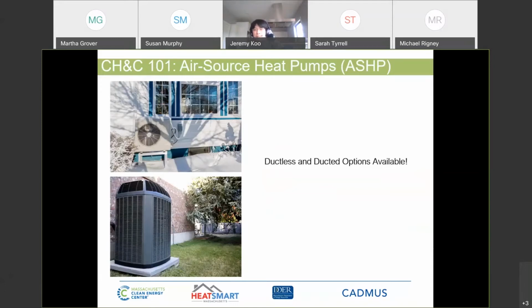Fortunately, in the last decade, there have been a lot of technology advances, including cold climate air source heat pumps, which provide high efficiency at temperatures of 5 degrees and lower, and can keep providing heat as low as anywhere from -13 to -22. That's just air temperature, not including wind chill. So these systems are certified and tested by one of the national regional energy efficiency organizations, the Northeast Energy Efficiency Partnerships, for their performance at those temperatures, and those will be the systems that will be primarily installed through the Melrose program so that they can provide efficient heating year-round.